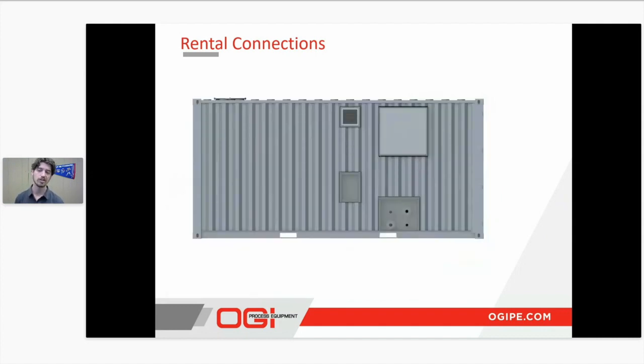Moving over to connections, the QuikWater can be installed via 5 simple connection points. First, we have our electrical connection, so your electrical disconnects will go here. All the QuikWater rentals that we have are going to be 460 volts, which is just standard for us. For any Canadian ones, we can design for 575. If you have a lesser voltage, we can change out the pump motors and make some changes to the control panel as well if needed.